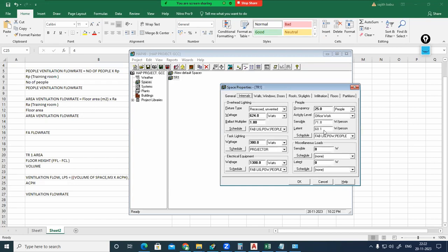71.8 and 60.1. If you are changing instead of office, dancing: sensible is 89.4, latent is 159.7. More, athletics: sensible is 208, latent is 319.